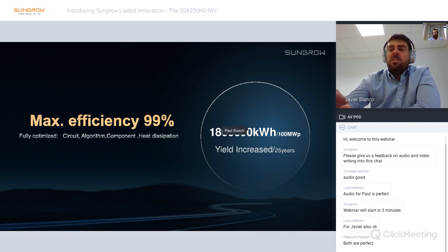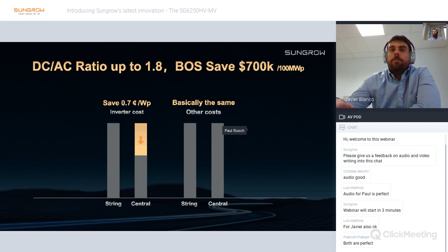Regarding Capex, here we can have a quick comparison of string versus central inverter. Mainly the Capex is still lower in the central inverter than in the string inverter, where the rest of the costs of the PV plant are basically the same, especially in big utility PV plants in flat terrain, where we are promoting this central inverter solution. In these cases OPEX is really similar, so the Capex is still making a difference in favor of the central inverters. So let's say in a 100 megawatt peak PV plant, we can still save around $700,000 with the central inverter. And let's remember, we can work with this kind of solution with a DC-AC ratio up to 1.8.